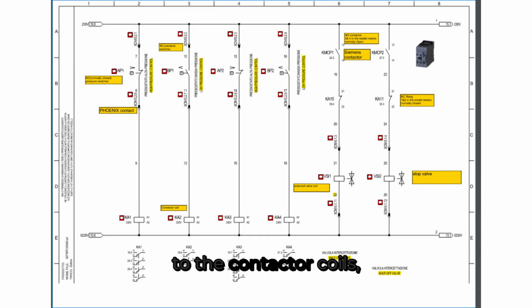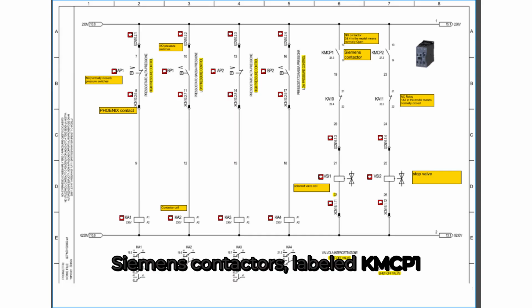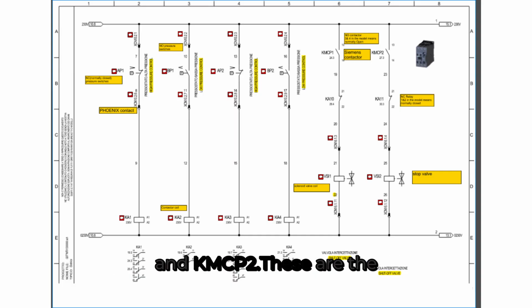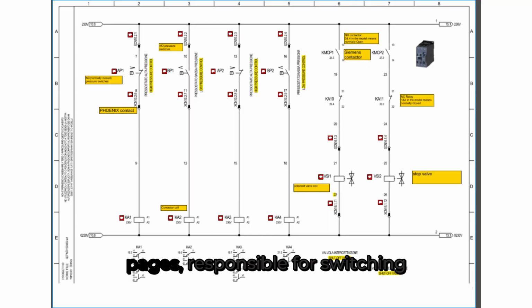The wiring then leads to the contactor coils, labeled KA1, KA2, and KA3, which are 230-volt AC relays. When these coils energize, they close the associated contacts shown at the bottom of the page. These contacts, in turn, enable power to flow to the compressor or the solenoid valves. You can see that KA1, KA2, and KA3 are arranged in series with the pressure switch circuits, creating a chain of interlocks that ensure the compressors only start when all safety conditions are met. Next, we have the Siemens contactors, labeled KMCP1 and KMCP2. These are the same contactors we saw earlier on the power pages, responsible for switching the main compressor motors on and off.